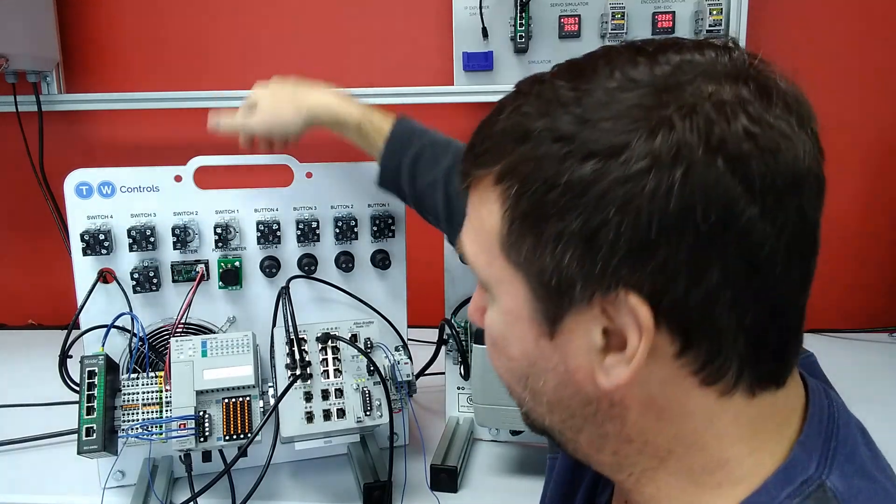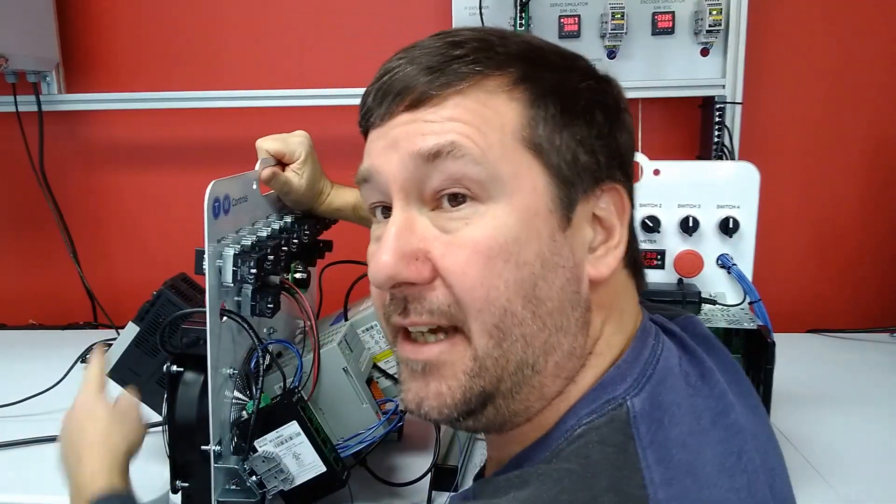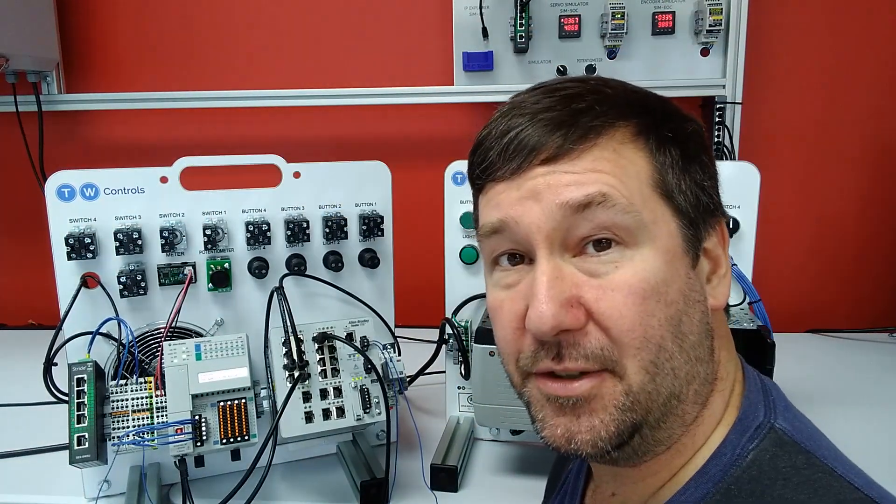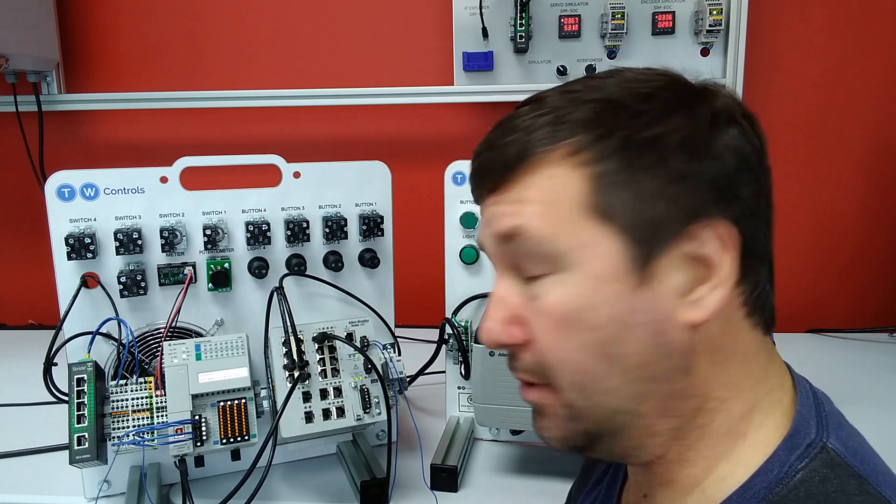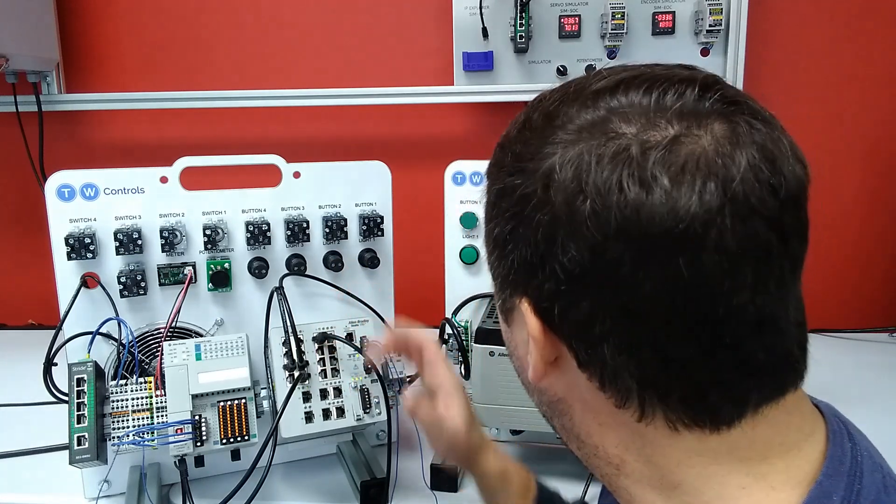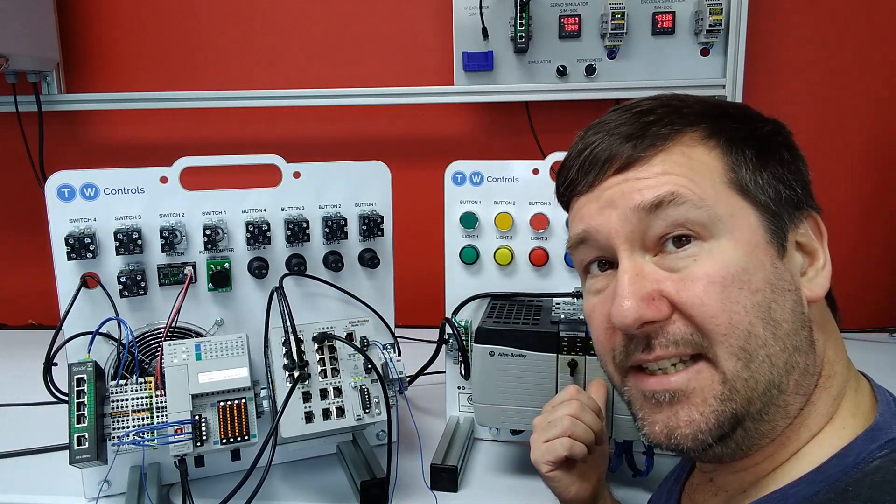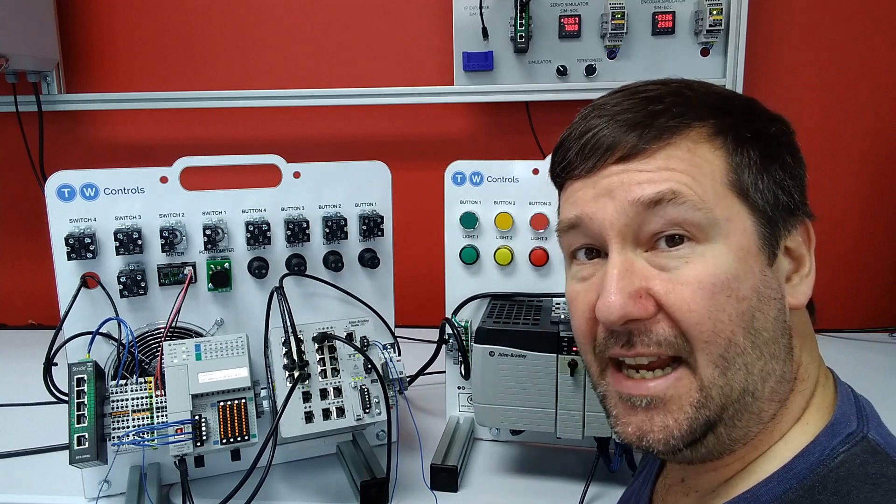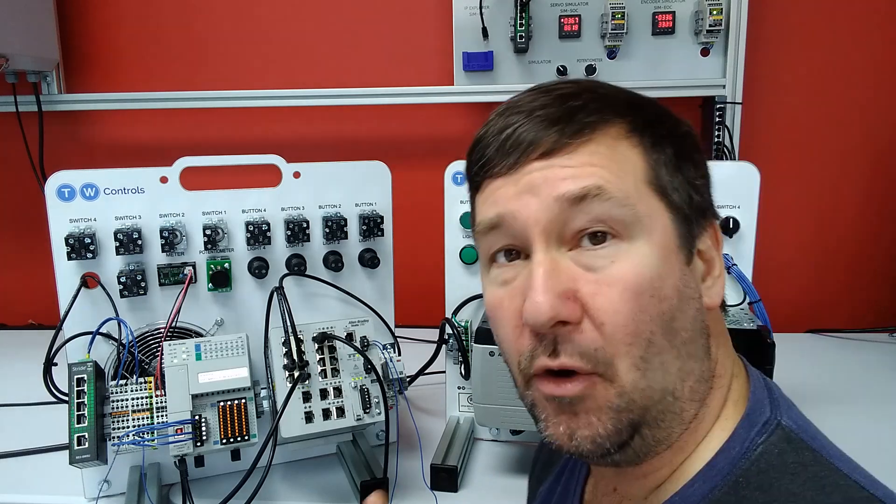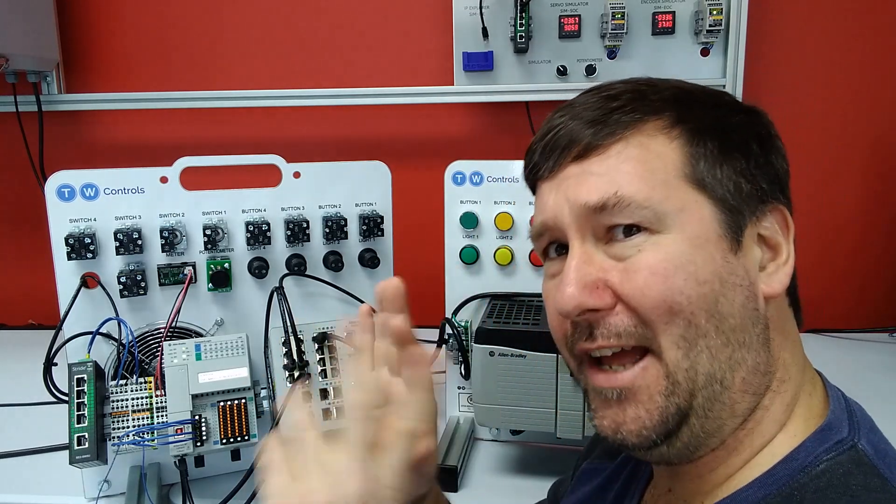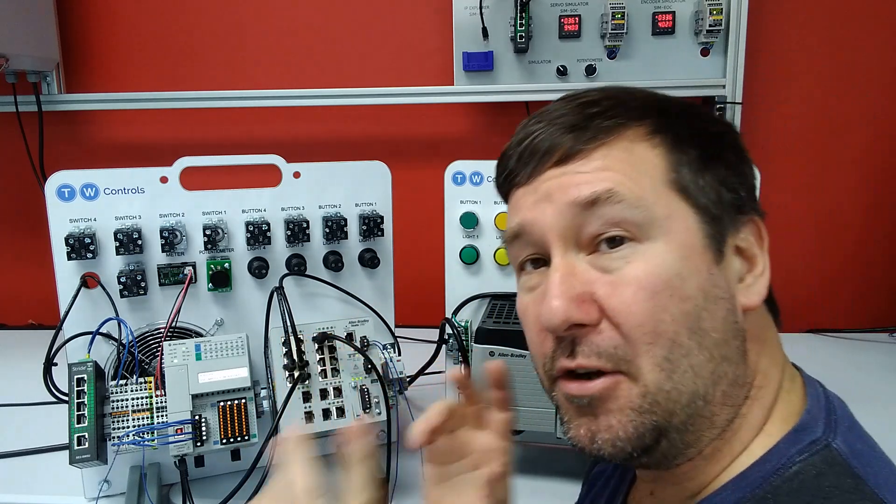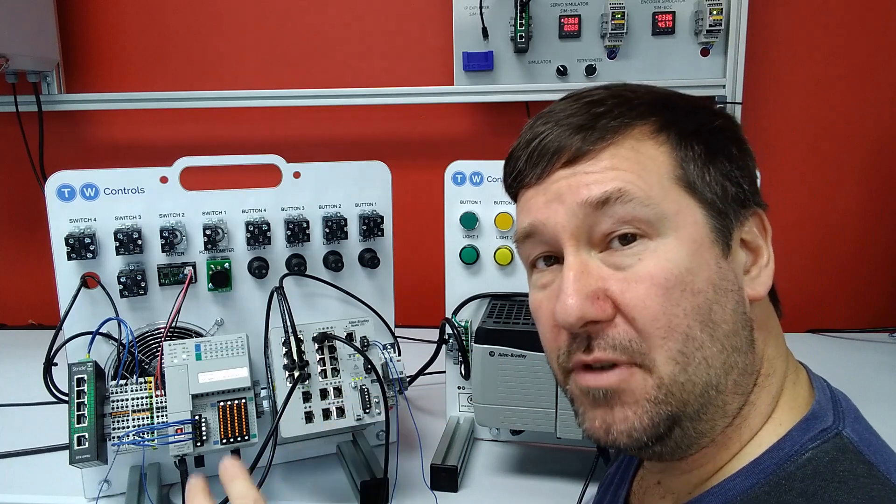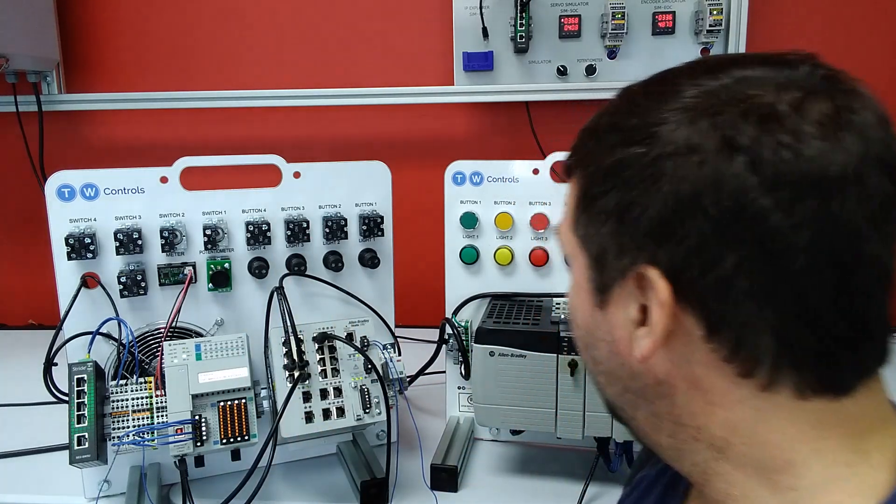So right now I don't have anything connected to VLAN 1. On VLAN 10, I have a compact Logix PLC, and that is configured for 192.168.10.41. And on the back of this, actually, let's see, we can just kick it around a little bit. You can see, yeah, right there is a drive. It's our PowerFlex drive, and it's configured for 192.168.10.142. But out of this section, which is our VLAN 20, we have our 1756-ENBT, and that's configured for 192.168.20.17. So as I have told you many times in previous videos, as Tim's rule, this is not a pure networking rule, your first three octets have to be the same, and your fourth one has to be unique for devices to communicate with each other.